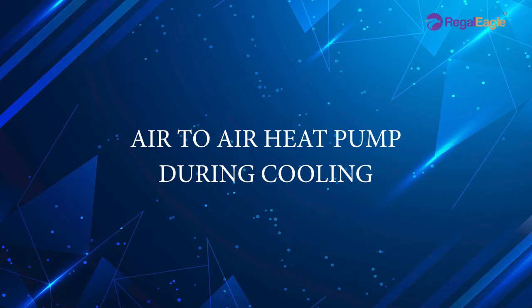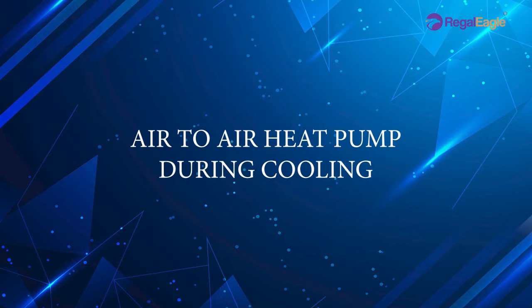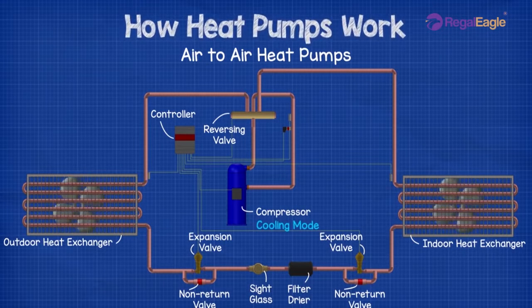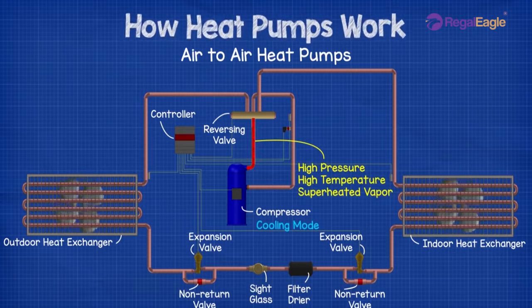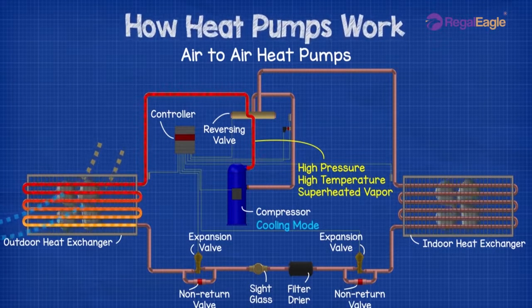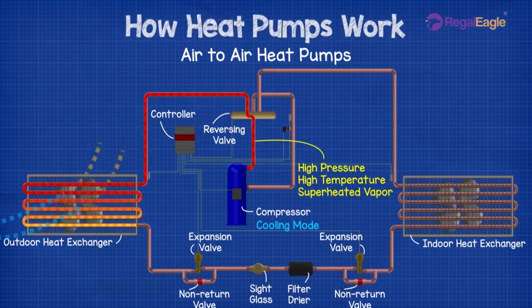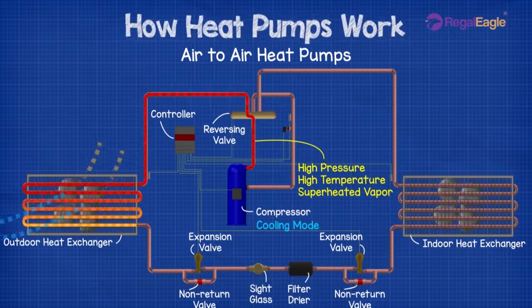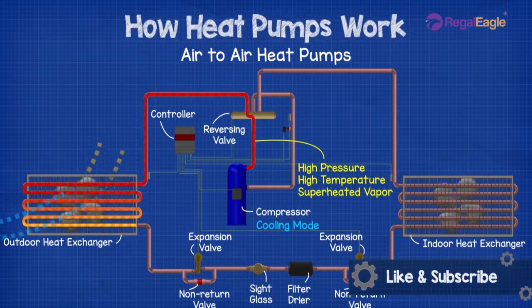During cooling, the air-to-air heat pump acts like a normal air conditioner. When the system is set at cool mode, the compressor forces the high temperature, high pressure, superheated refrigerant vapor through the reversing valve, which transfers it to the outdoor heat exchanger. The fan of the outdoor unit blows ambient air across the refrigerant coil, so it carries away the heat of the refrigerant. The refrigerant condenses to liquid, having lost most of its energy. The outdoor unit is considered a condenser, since it condenses the superheated refrigerant to a lower temperature, high pressure liquid.